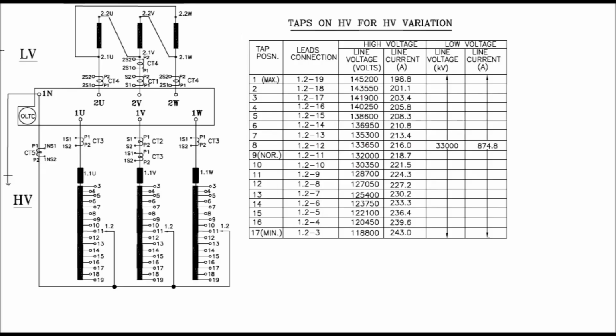So in this nameplate, the tap on HV for HV variation has been shown. Here the 33 kV or LV side voltage is taken as a constant, and the tap position is changed from 1 to 17 number, and by connecting the lead connection from 1.2 to 19.